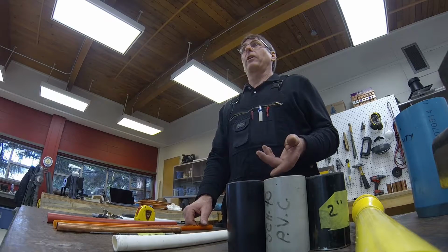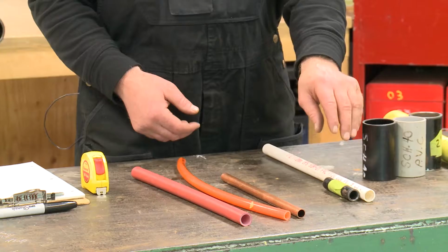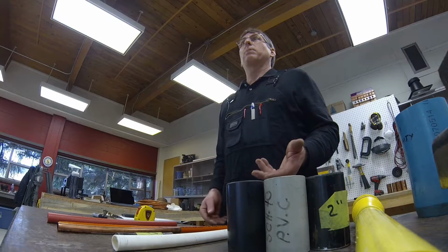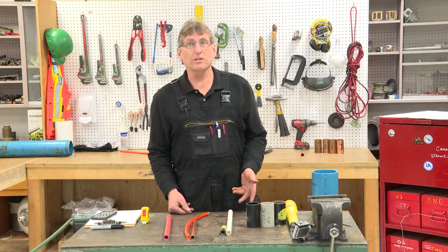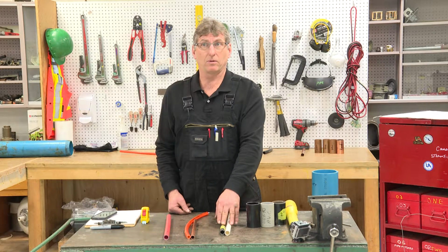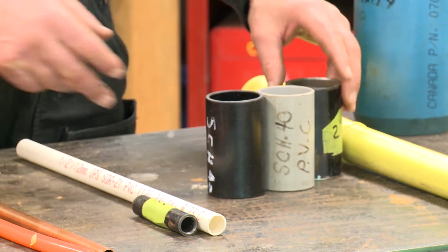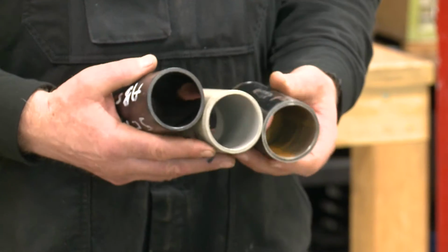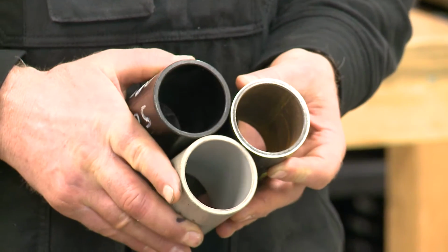Well, let's start with a quick refresher on plastic sizing. Remember, you're going to find plastics that are sized to both the IPS system as well as the copper tube size system. And likewise, plastic wall thicknesses use more than one system. For starters, we've already seen some examples of plastic pipe which was sized to the IPS system, which used the same steel pipe schedule system to rate the wall thickness. Here are a couple of examples of PVC and ABS, which when compared to their steel counterpart, you can see that the wall thickness is pretty much an exact match.